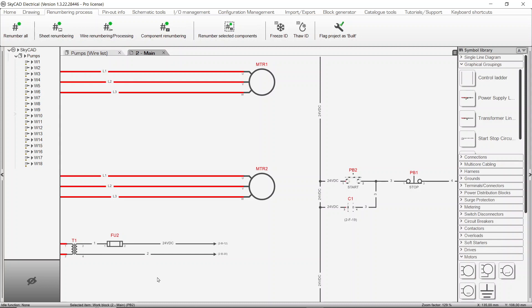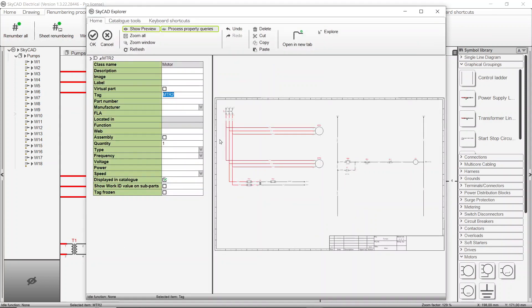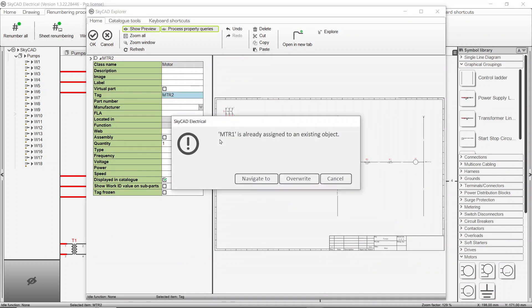Something else that's important to know is that when you try to force a number manually, SkyCAD's uniqueness control will nonetheless ensure that all elements have unique numbers, as they should. To demonstrate, if we try to manually number this motor's tag to MTR1, a message box pops up saying the value is already used and offers you three choices: Navigate to, Overwrite, and Cancel.